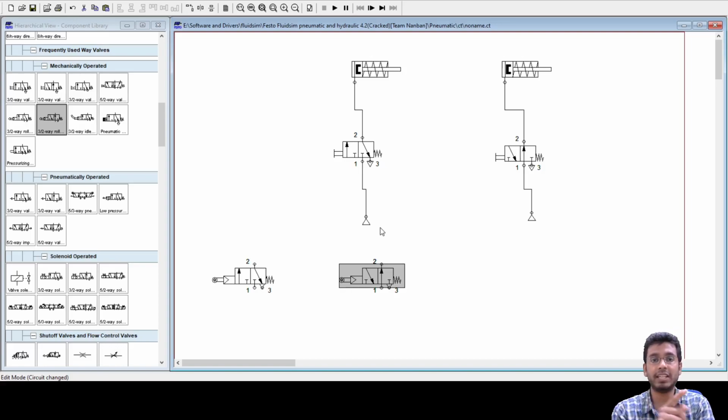For example, when my cylinder is extending, the completely extended position of the cylinder triggers my movement backwards. Okay, and for that we require a pneumatic signal to actually shift the valve. So in that case, we are using a normally closed valve. Now suppose we are using a normally open valve, say with this valve we are controlling some other cylinder which in its initial position has to be in its extended position, and the moment my cylinder, for example, say I'm having two cylinders.